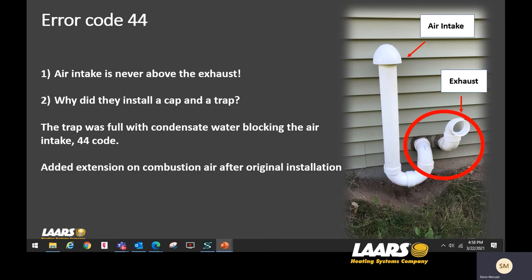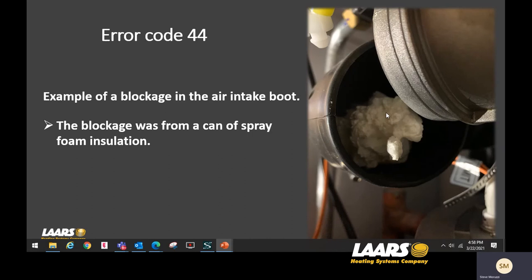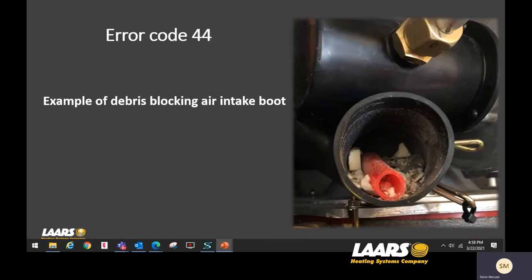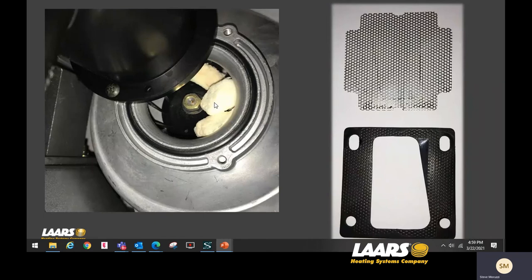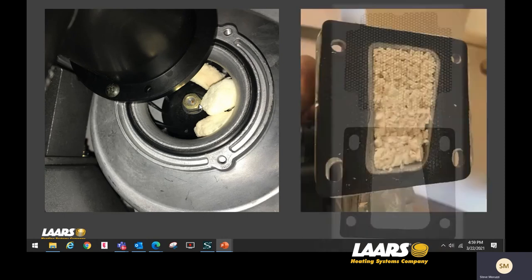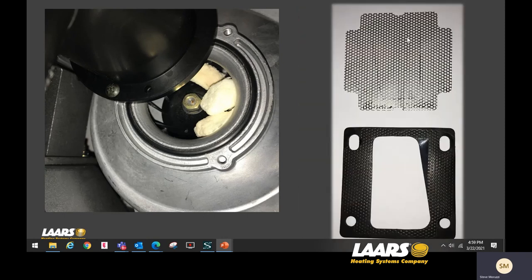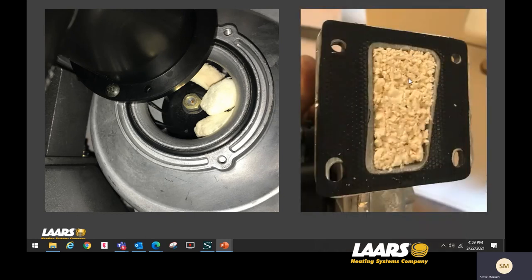Here's another example of a blockage in the air intake boot from a spray foam can — pieces broke free and got sucked into the combustion air intake, making it to the mixing station and causing a blockage and a 44 error code. Another example: during installation the boiler was hung on the wall but not yet vented, so construction debris was getting down inside the combustion air intake and the exhaust. When they went to start it, all the debris got pulled right into the mixing station. In another case with small packing pieces, whatever gets drawn in gets chewed up — on a 140 model it ends up on the mesh screen, giving a 44 error code.